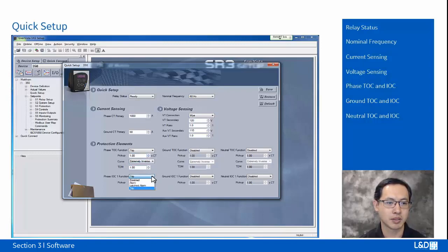We can also set up the phase IOC for the trip and pickup levels. If you want more detailed settings, you need to go to that element to set up more information like the delay, the blocking, and the directional. But if you just need basic protection, just operating pickup levels, this can quickly set up a relay into service without going to the detailed setup screens. So click Save, so all this information is saved.